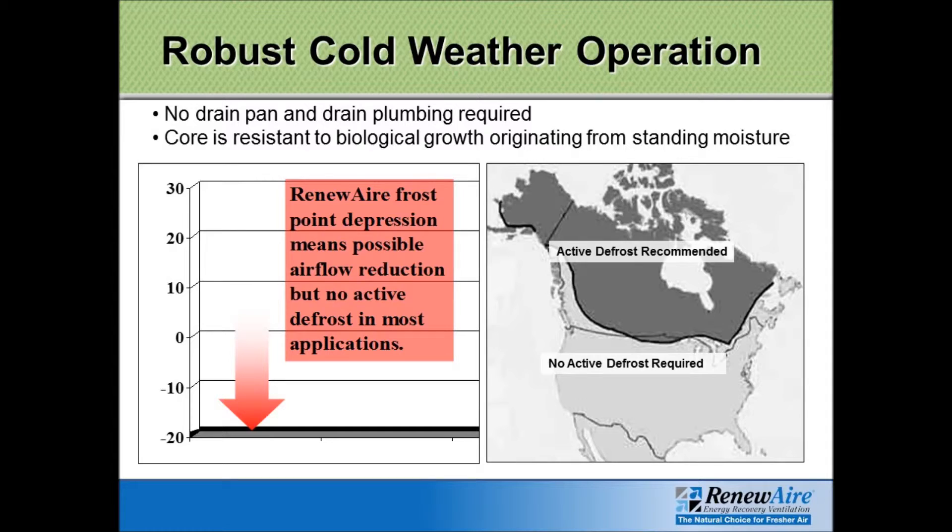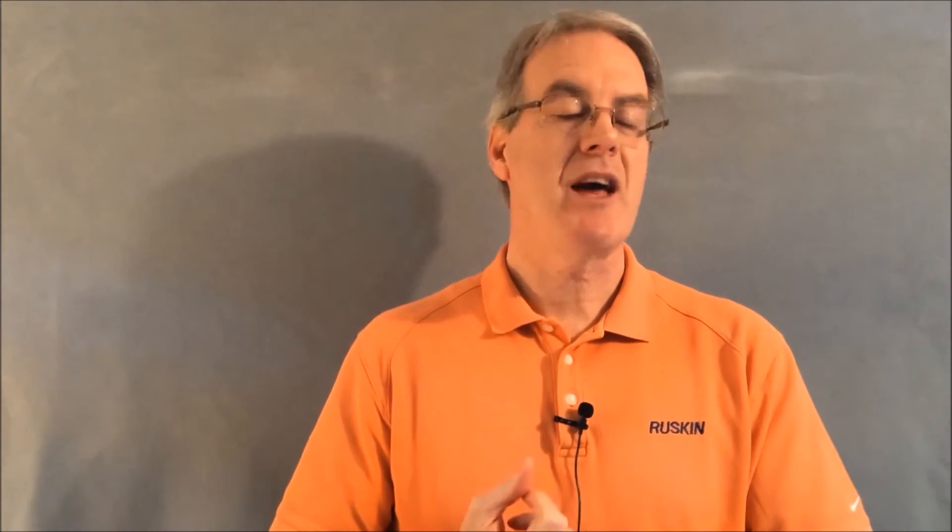With a desiccant wheel, if the temperature in your area gets down to freezing, you have to be concerned about frost control. With the RenewAire unit, the only time you need to worry about frost control is when two conditions are present: the outdoor air temperature has to be at least minus 10°F, and the indoor relative humidity has to be 40%. When it's that cold outside, it's almost impossible to have an RH that high in the building. So basically, in all of the United States, there's simply no concern about adding expensive frost control measures to your ERV. RenewAire simply operates without having to worry about that.